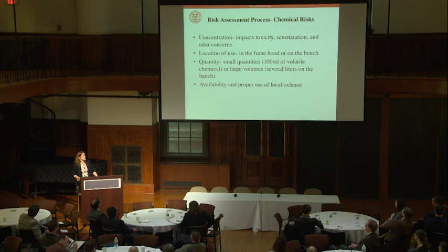The location of use - are they using those hazardous chemicals in the fume hood, or on the bench top? Let's say there's a piece of expensive equipment they have to use out on the bench, they can't use it in a ventilated enclosure. And then the quantities - very small quantities, 100 mils, the little squeeze bottles of acetone, or is it several liters, larger quantities?